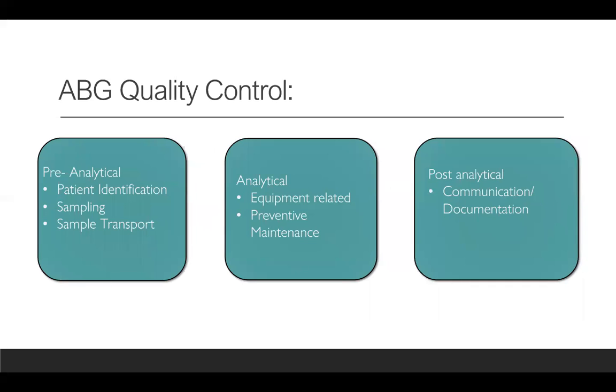We always want our ABG results to be accurate, and one way that we can make sure of this is with quality control. We can break up our ABG quality control into three different sections: pre-analytical, analytical, and post-analytical. In the pre-analytical quality control, we can include patient identification, so making sure we're using the correct patient labels. As we stated previously, we want to make sure that our sampling is done correctly, so make sure that we have arterial blood and not venous blood. We want to make sure that our sample gets transported correctly and in a timely manner.